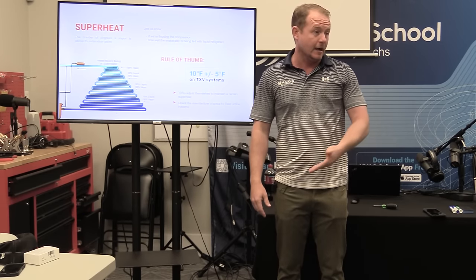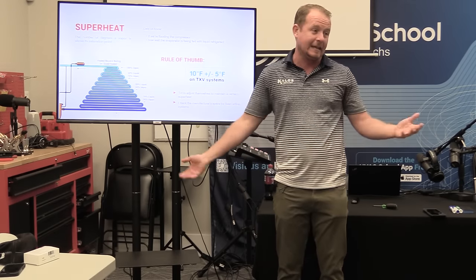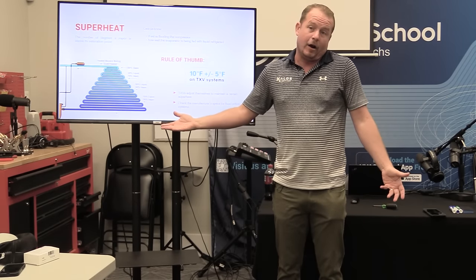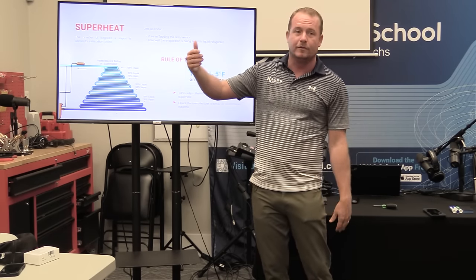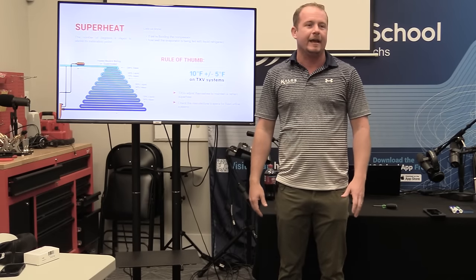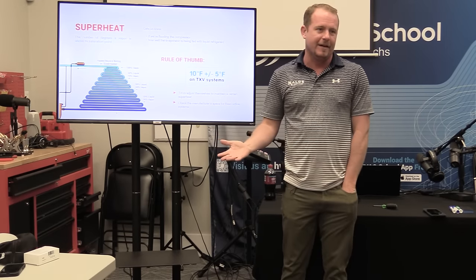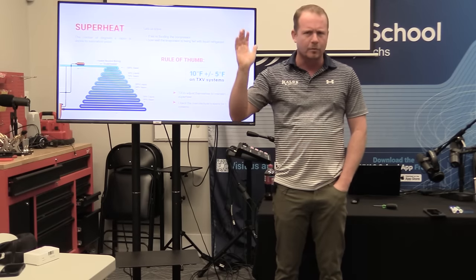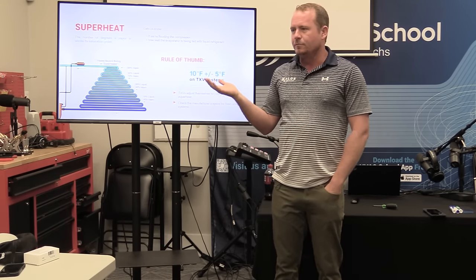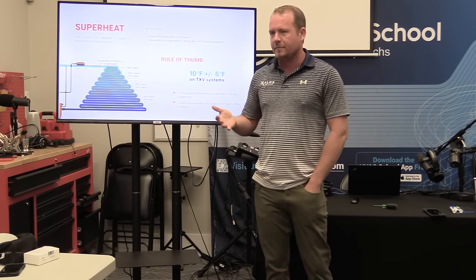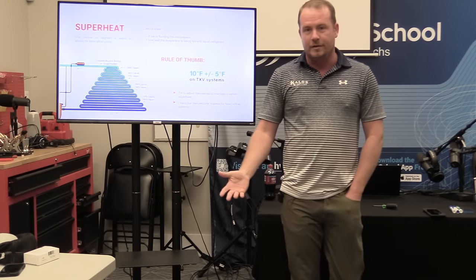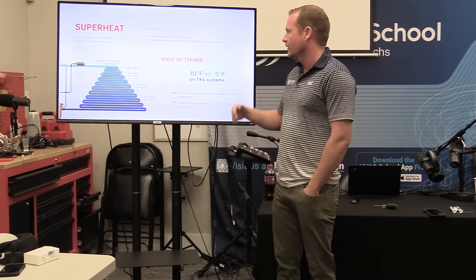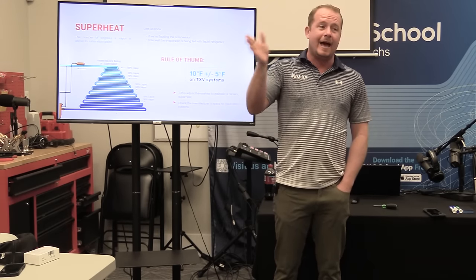25 degrees superheat is not good for the compressor — it means the compressor is going to run hot its whole life. But sometimes we don't have control over that, like in communities with insanely long line sets. They are going to have abnormally high compressor failure over their lives because of that. It doesn't mean they'll fail in five years — they might fail in 12 years when they would have normally lasted 15. A lot of this stuff we say is bad may not cause a problem for a really long time. It's just like pulling a good vacuum — old timers say they never used a micron gauge and never had a problem. But it's not that the system explodes 10 minutes after you leave; it means you've taken years off its life.